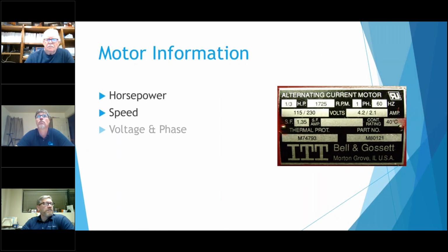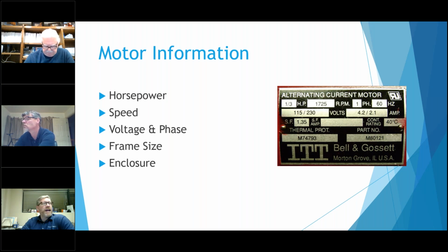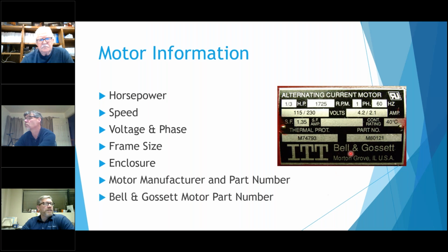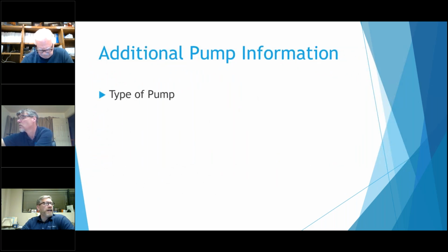Some of the motor information that we might ask for if you don't have the name tag: horsepower, speed, frame size. There is a B&G part number that we can cross over to our pumps, or to some of the booster pumps. We might ask what type of pump you have. Casting numbers are also very helpful. You can see on here, this is P85923. This will correspond to at least the size and type of pump, to that pump model.